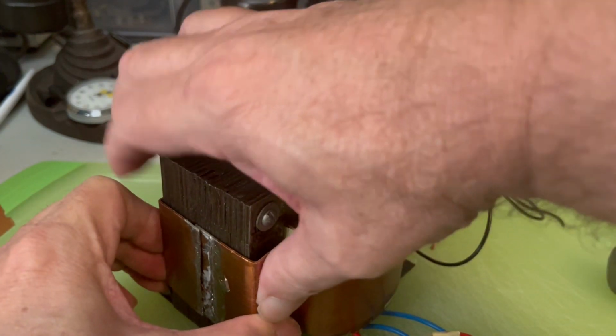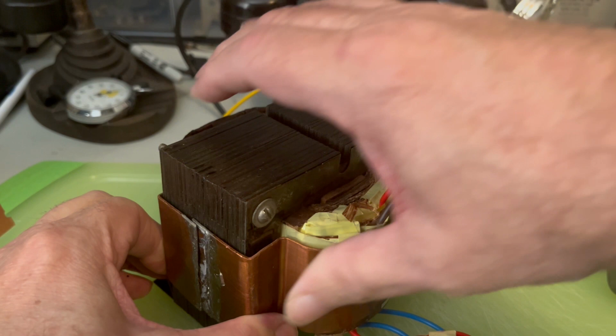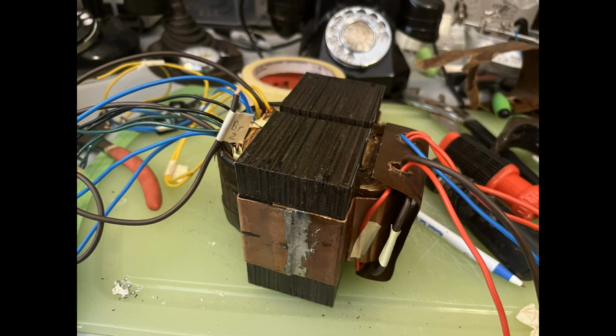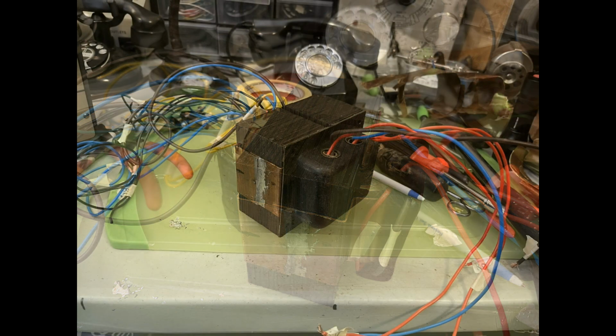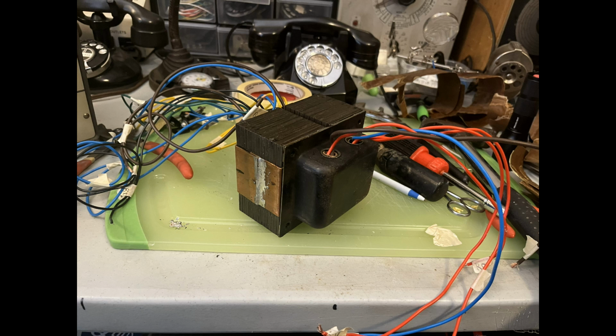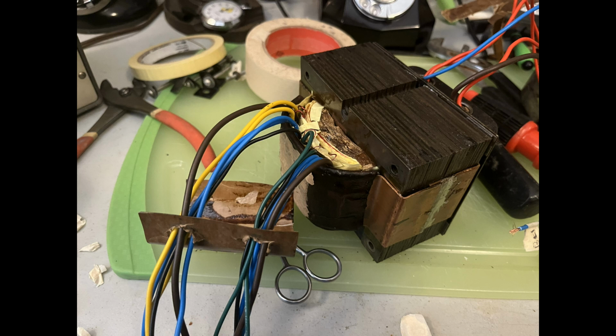Eventually I would resort to using a clamp and one of those little butane torches to reinstall the copper band. In this image, I'm threading the conductors back through the cardboard insulation that runs between the coil assembly and the outer casing. Those same conductors are then threaded back through the holes in the casing as it is folded on top of the core and reconnected to the laminates. The process is repeated for the other side.